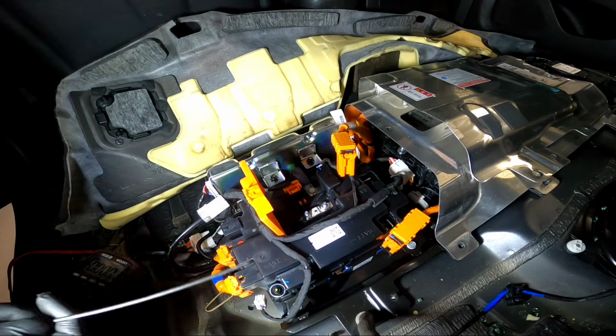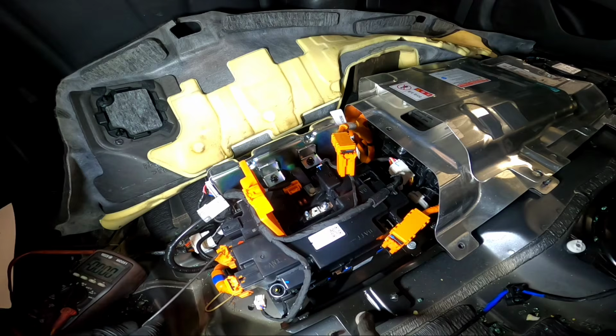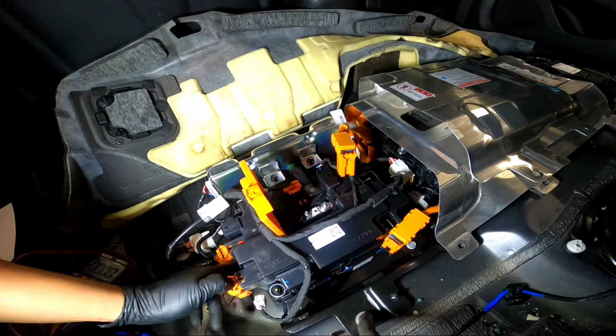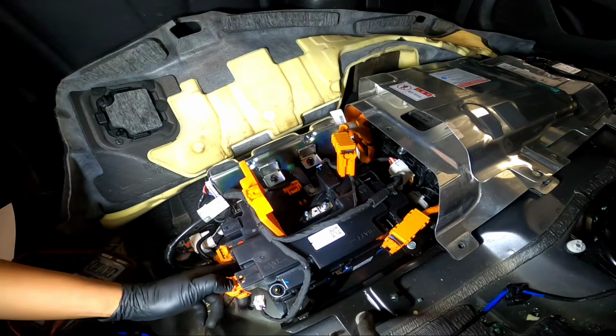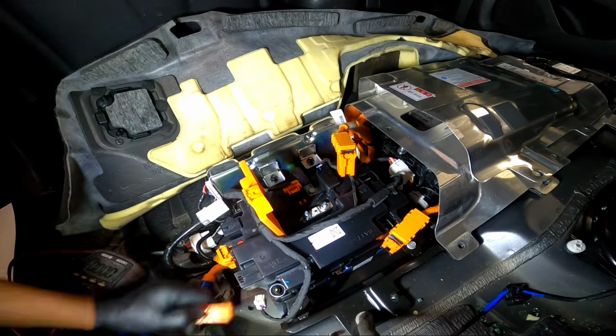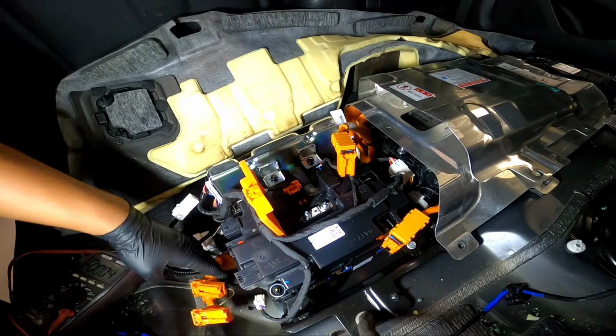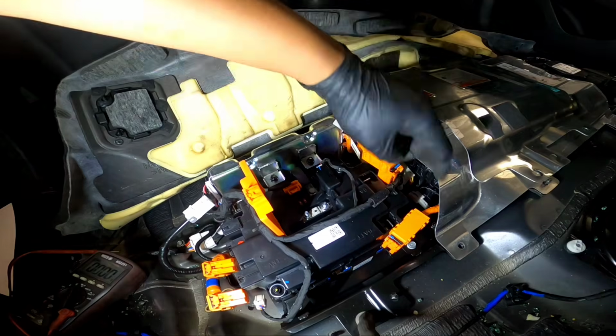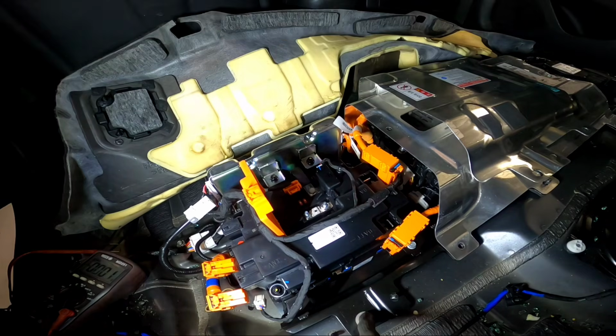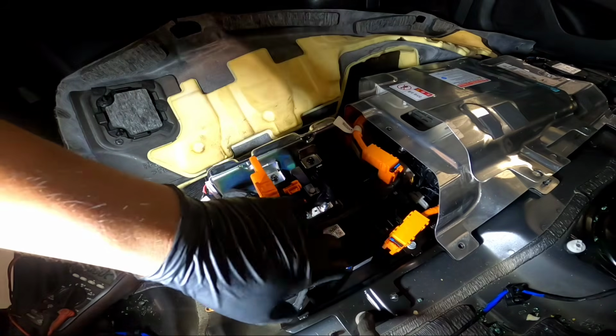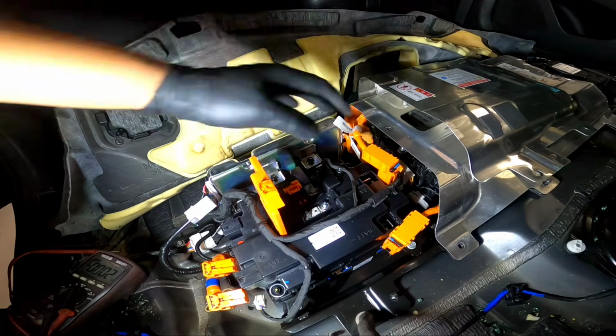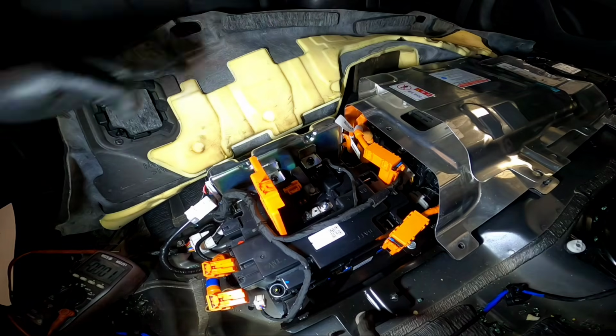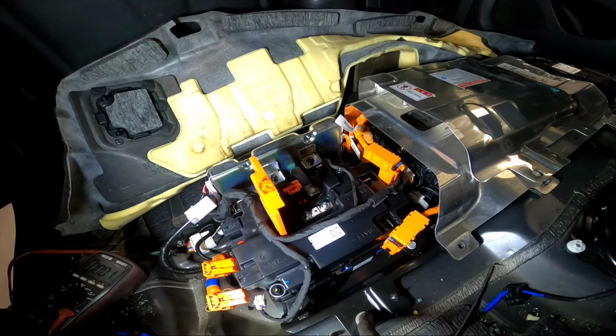Now if you're still hesitant, well, we already shut off the whole thing, right? So now at least the confidence level of removing the high voltage system is good. So okay, that's out there, right? The only time voltage will show here is when the relay is on. And of course you still have these guys here, so be careful. So if we measure that, do we have a potential voltage coming out there? Let's see, because it should be open right now.